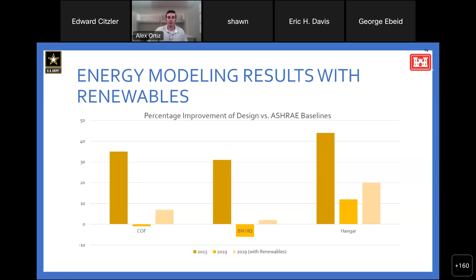So the impact of this is going to be significant because we are not meeting that 30% mark in any of our cases, and even using higher efficiency equipment, I'm not sure if we would be able to hit that 30% mark. So the CFR, as I mentioned earlier, states that the design must have the highest level of energy savings while being life cycle cost effective and meeting 90.1. So it's basically saying that we don't necessarily need to meet that 30% mark as long as we are LCCE and complying with ASHRAE 90.1.